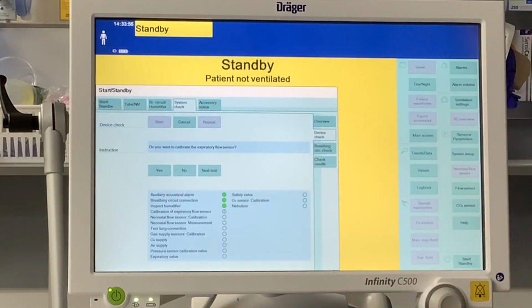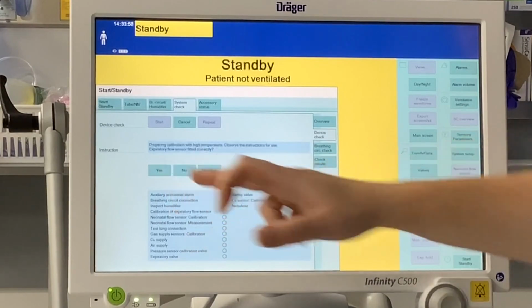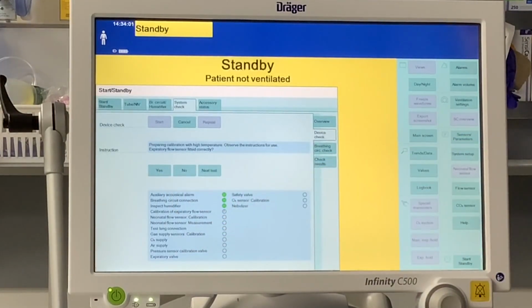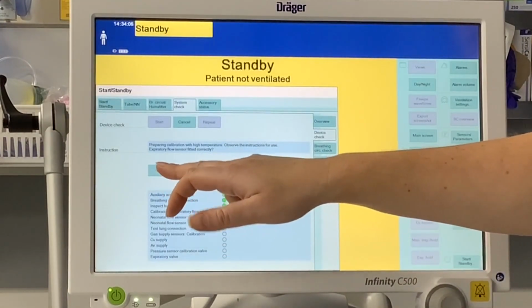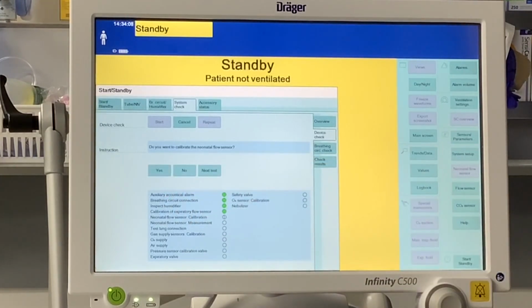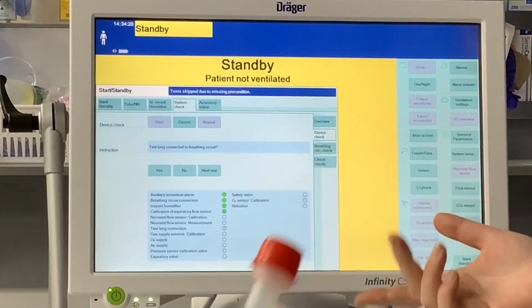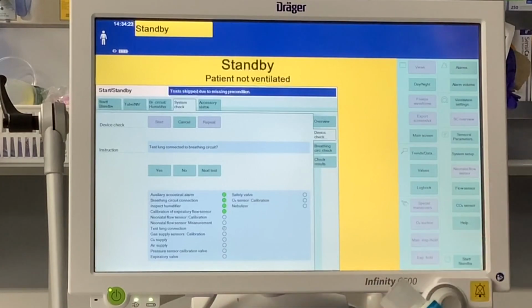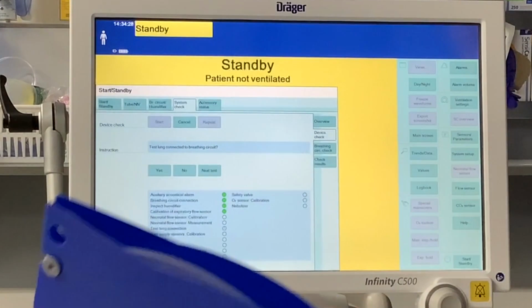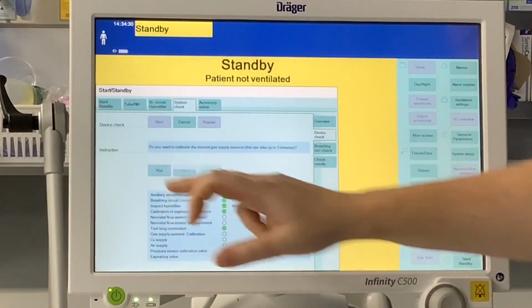And do we want to calibrate the expiratory flow sensor? Yes, we always do. And it's going to say, is it fitted correctly? Yes, we know it is because we put the circuit on previously. And do we want to calibrate the neonatal flow sensor? In this case, no, because we have it set up as an adult ventilator, so we're going to say no. And now, is the test lung connected to the breathing circuit? So what we're going to do is take that part off, connect the test lung to the circuit, and press yes.